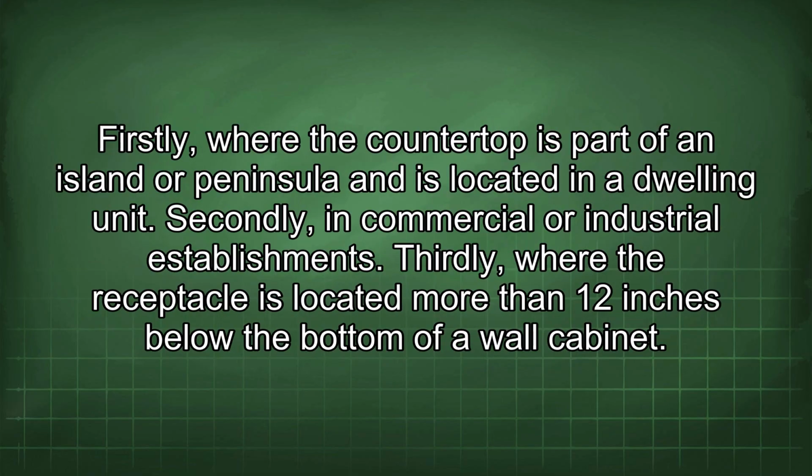Firstly, where the countertop is part of an island or peninsula and is located in a dwelling unit. Secondly, in commercial or industrial establishments. Thirdly, where the receptacle is located more than 12 inches below the bottom of a wall cabinet.